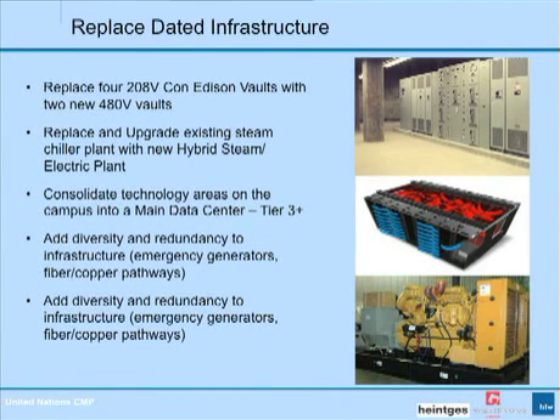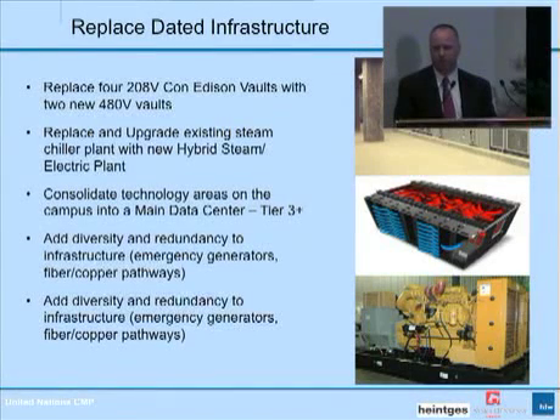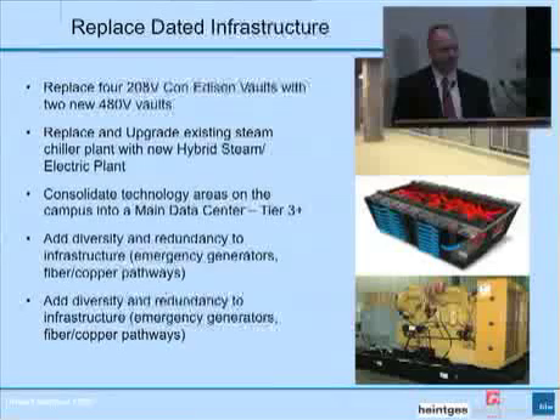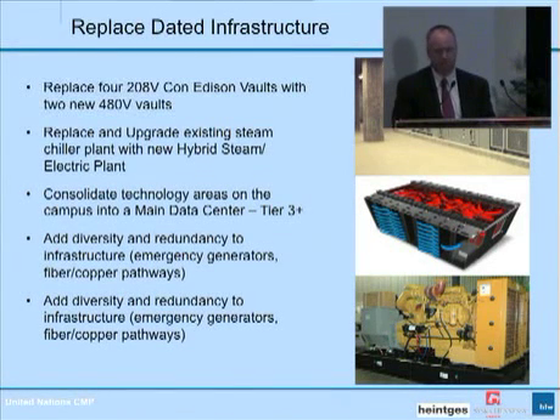The existing campus is served by 4 208 volt vaults. They're located throughout the campus. That distribution is over 50 years old. The wiring and the Con Ed feeders have been failing often. We're replacing them with 2 transformer vaults, 6 times 2500 kVA, in 2 disparate locations around the campus, north and south. We're replacing the existing Con Ed steam chillers with a hybrid plant that will allow us to use the most efficient source at the time, using real-time data for energy costs.